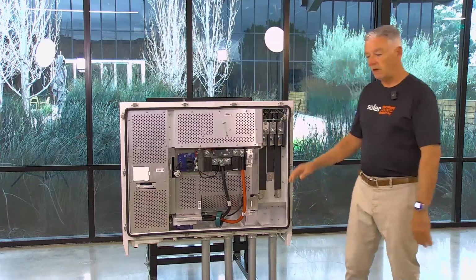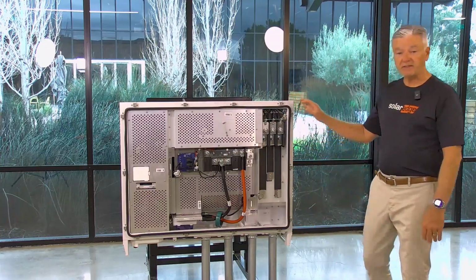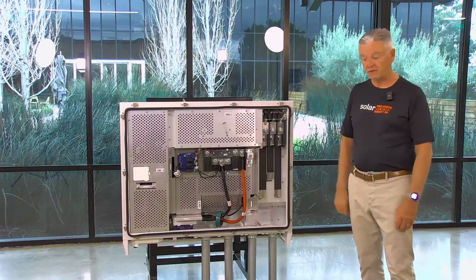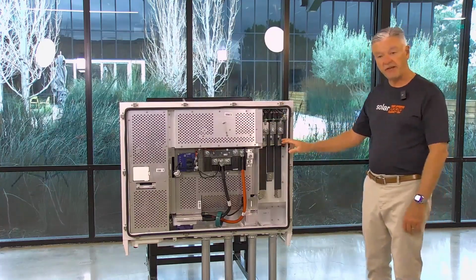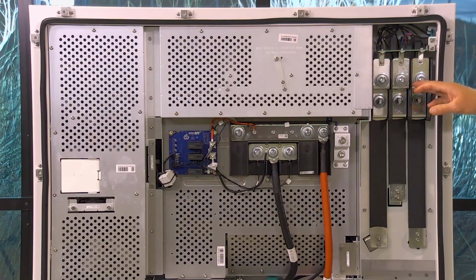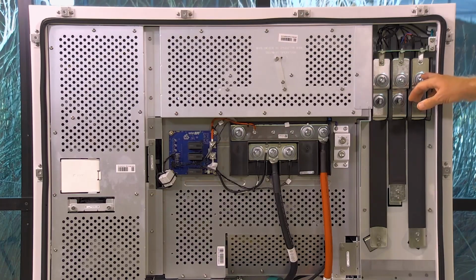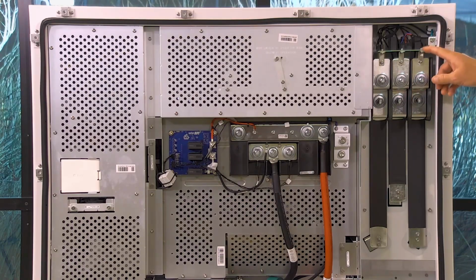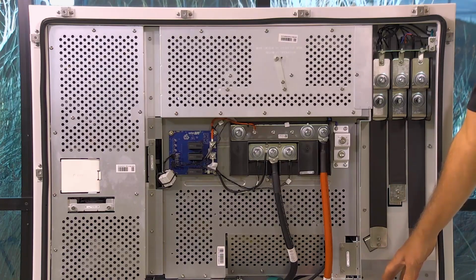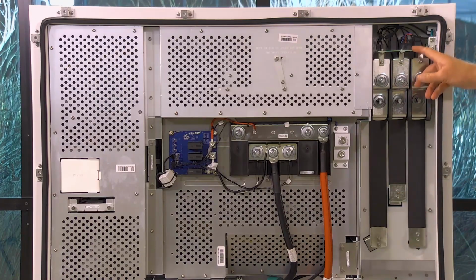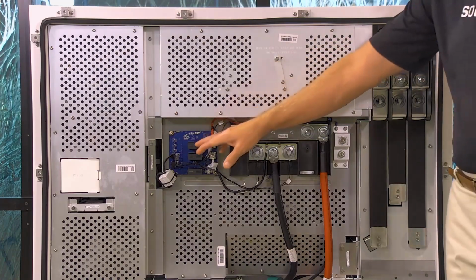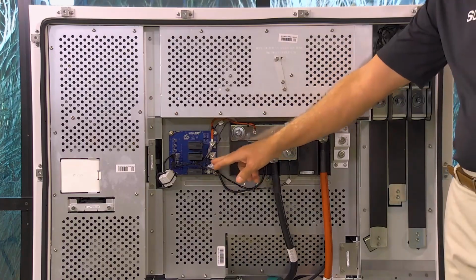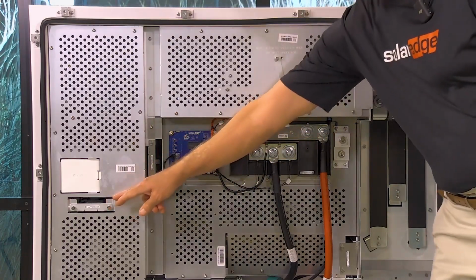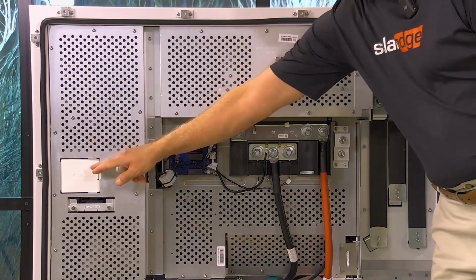All right, now that we have the cover off, let's take a look inside and see what some of these components are and how you interact with them. On this side right here is the AC terminal blocks. This is a dual terminal block for connecting parallel circuits, up to 2 circuits, up to 600 kcmil conductor, either copper or aluminum. Down here is the ground terminal bus bar. Here are the AC surge protection devices. Moving over here, you see the DC surge protection devices, 2 fans that are field replaceable, and auxiliary fuses for the auxiliary communications board.